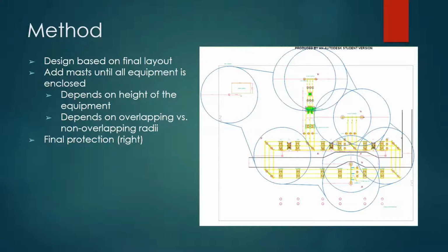So if they weren't overlapping, they offered more protection because IEEE found that it was more likely that lightning was going to strike that higher mast than it was to strike anything between those masts. So then we just kind of kept adding masts to our design until everything was enclosed, and you can see our final protection there on the right. It has a total of 9 lightning masts.